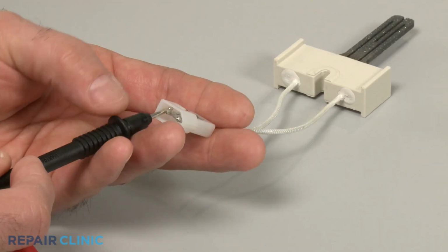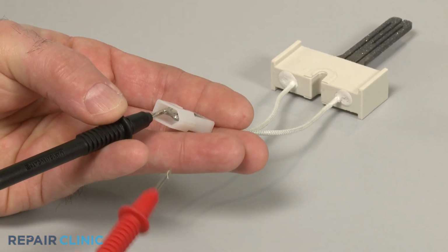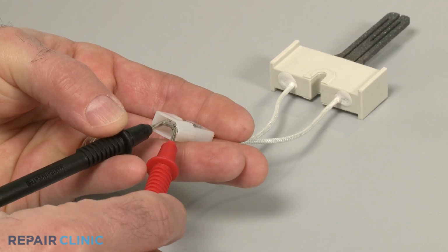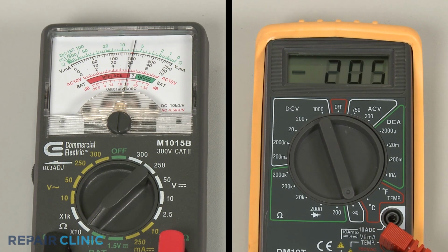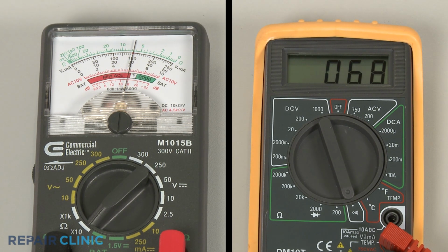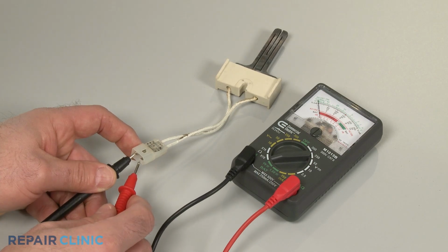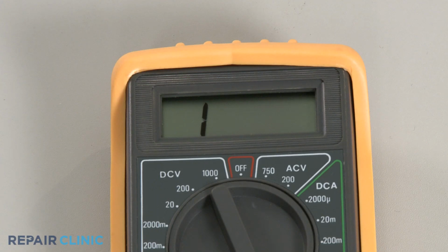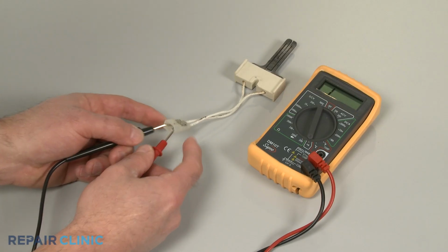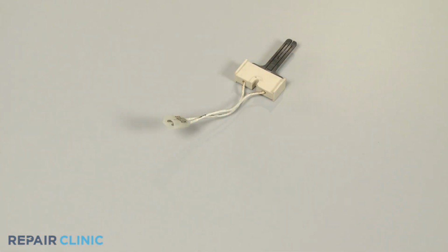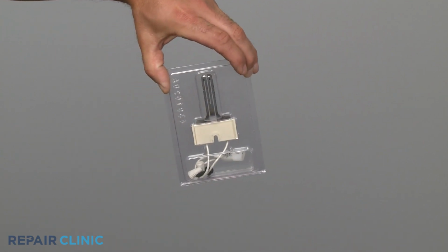Use a probe to touch one of the igniter's terminals, and the second probe to touch the other terminal. If the meter reading shows a result between 50 and 400 ohms of resistance, the igniter has continuity. Be aware that the high resistance of the igniter will probably prevent a meter tone. If the needle does not move, or the digital display does not change significantly, there is no continuity, which means the igniter is burned out and will need to be replaced.